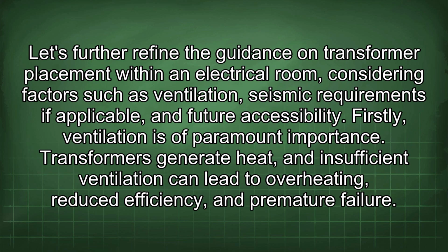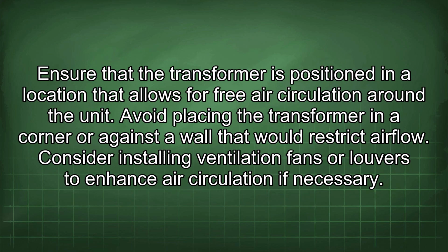Let's further refine the guidance on transformer placement within an electrical room, considering factors such as ventilation, seismic requirements if applicable, and future accessibility. Firstly, ventilation is of paramount importance. Transformers generate heat, and insufficient ventilation can lead to overheating, reduced efficiency, and premature failure. Ensure that the transformer is positioned in a location that allows for free air circulation around the unit. Avoid placing the transformer in a corner or against a wall that would restrict airflow. Consider installing ventilation fans or louvers to enhance air circulation if necessary.